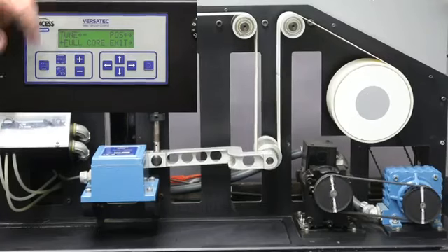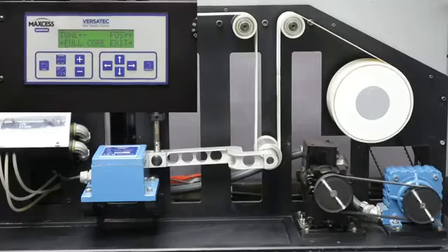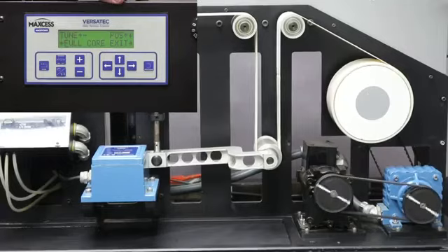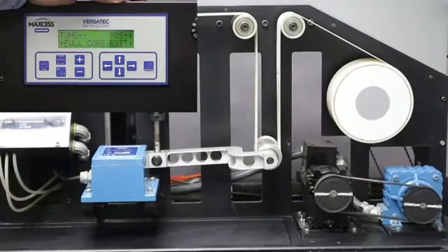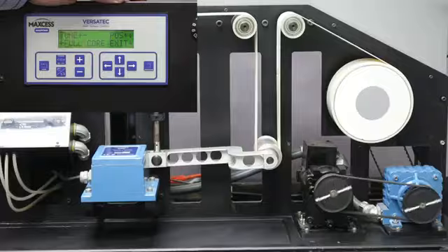Now the next thing I'm going to do, under full roll, is hit the minus key. I'm actually going to hold the minus key. What this is going to do is increase the gain. The gain is how much the control reacts to a given error. So the more gain I put in, the more unstable it will become because it will start overshooting. It's going to react too much.